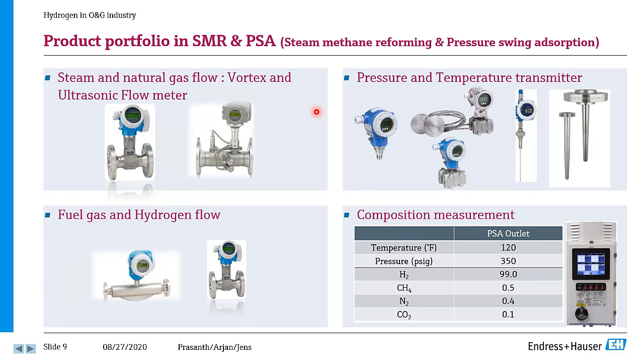Coming to the right side of the slide, pressure and temperature transmitters - we offer a complete range of pressure, differential pressure, and temperature transmitters. One critical topic when we talk about pressure transmitters for hydrogen is the suitability of the diaphragm, the membrane we use. We have devices with gold plating, which is suitable for hydrogen applications.